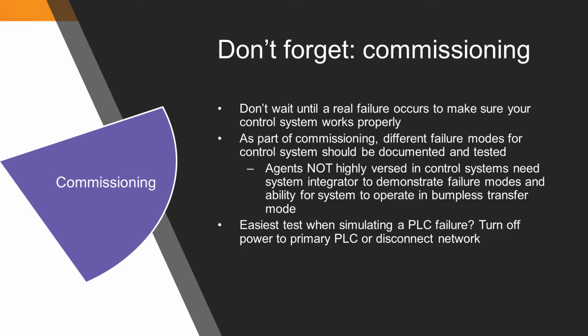mission-critical facilities typically employ a third-party commissioning agent, a separate party not involved in the design nor the development and installation of the control system. They'll have no inherent biases, and not being familiar with the design, they're there strictly to put that system through its paces and provide the owner with peace of mind that should the system be called upon to function under one of the failure modes, it will do its job properly.